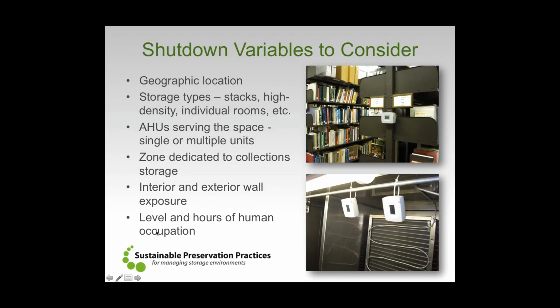If we've got AHUs that serve the space, we need to know which ones to turn off or make sure that the entire zone is working the same way. And if we have a zone that has to do with people, an occupied zone or a multi-use zone, we have to think carefully about what it is that we're turning off and whether or not people are still in those spaces when we're looking at shutdowns. Interior and exterior wall exposure: obviously, spaces that are away from the exterior portions of the building certainly won't see as much load or as much fluctuation on system shutdown, and also keeping in mind human occupation and comfort.